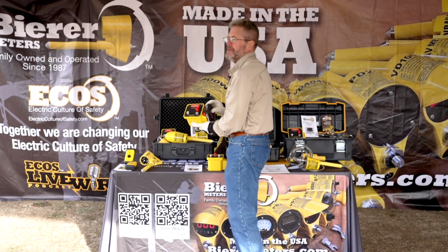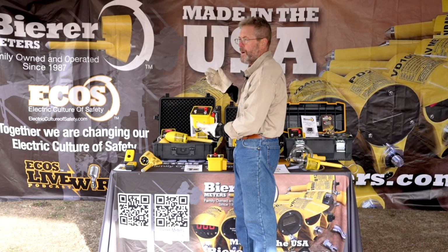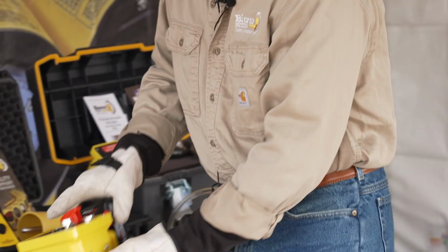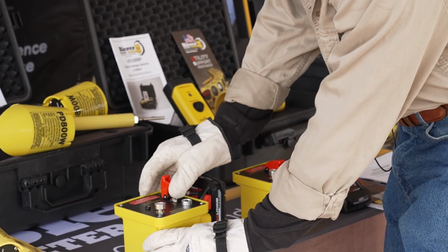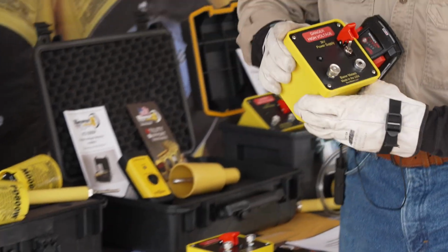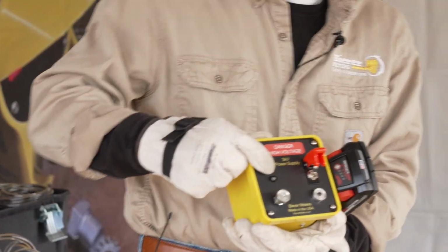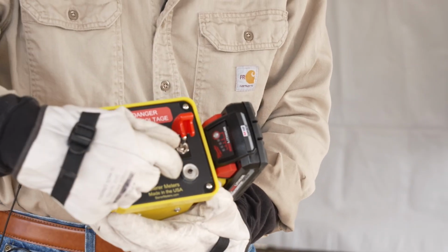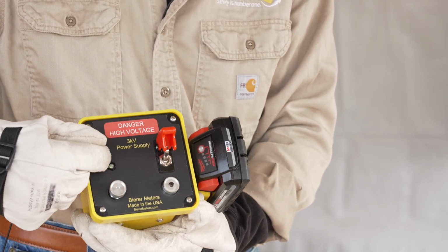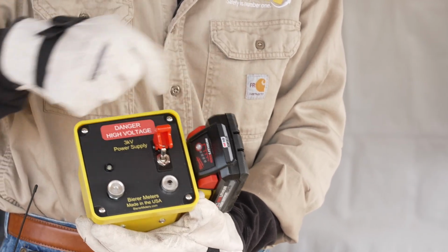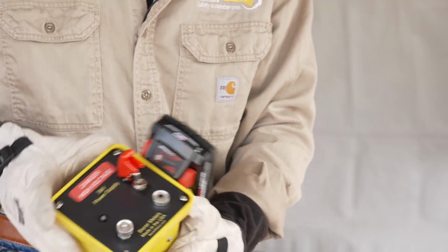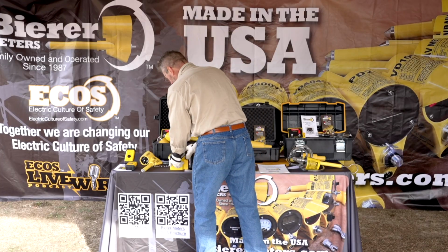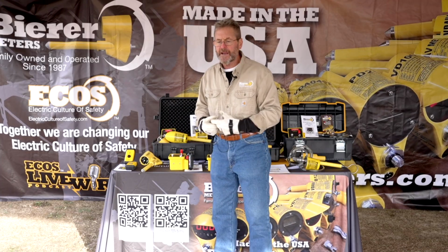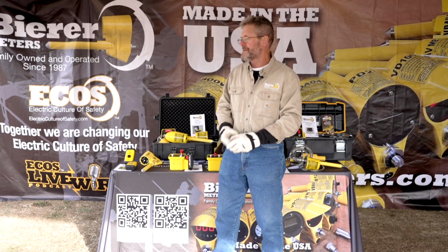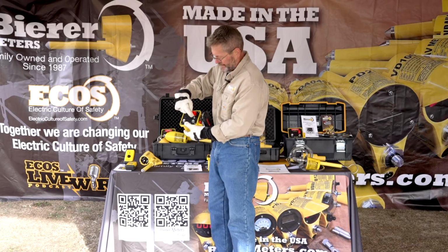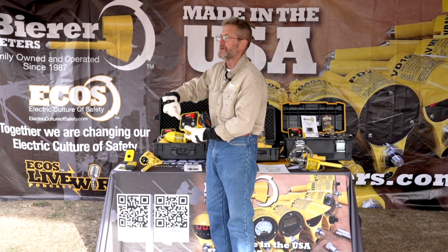We've got our battery. We know that the battery is good, 4 bars. Plug it in, and we're going to go ahead and turn that on. Now you see that plunger is up, so it's not energized yet. The light's green. Battery's good, light's green, tool's ready to be used. Let's check it out. 3 kV power supply. Remember, this is what we recommend for all your corded devices. We have our ground plane and we have our hot phase right here.